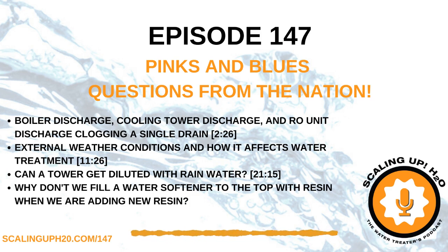Normally, the amount of rain that affects conductivity is minimal at best. But again, it depends on the system. It depends on how much rain we're getting. So you need to know the system better than anybody else. And if you can, without a doubt, say that there's nothing else wrong with the system, it is bleeding properly, it is making up properly, then perhaps you have one of those systems that is affected by rain.